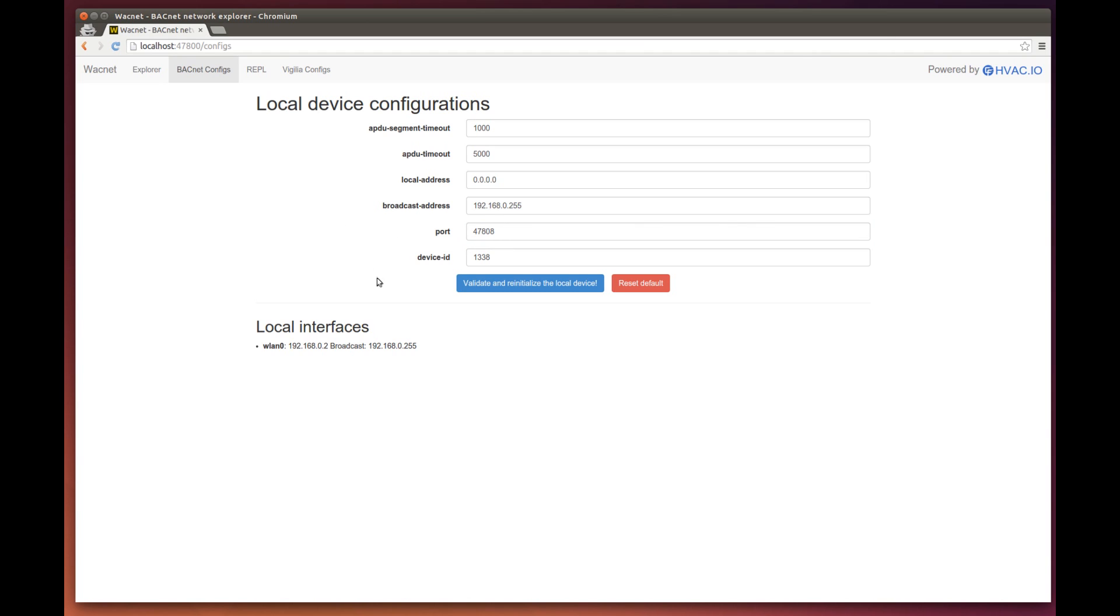The device ID is the most important configuration. On every BACnet network, only one device can have a given ID.